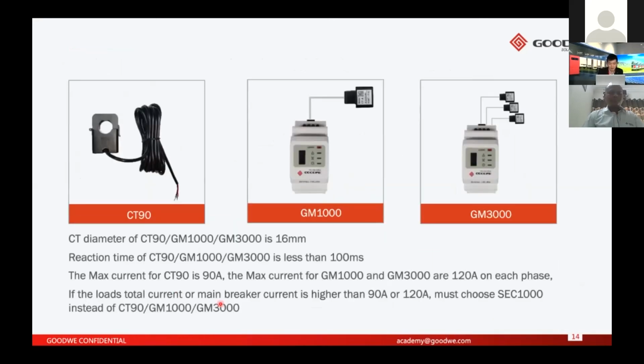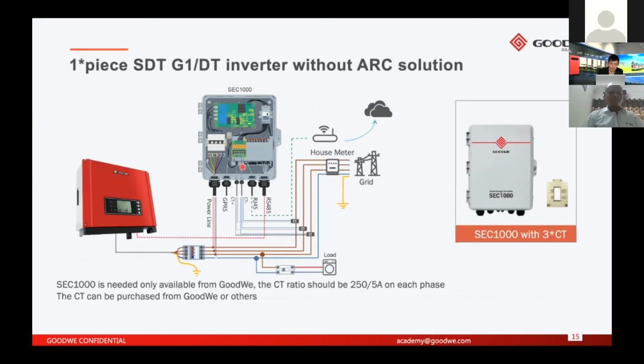So here are some parameters for each device: the reaction time, the CT diameter, and the maximum current for each one. So if your total load current or main breaker current is higher than our device's limitation, you need to use the next one. I will introduce the SEC1000. So it's this one, the SEC1000. If your inverter is one piece, SDT G1 or DT without ARC, you need to use the SEC1000 from GoodWe.